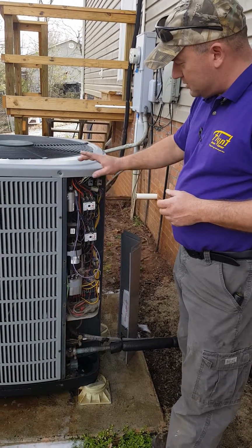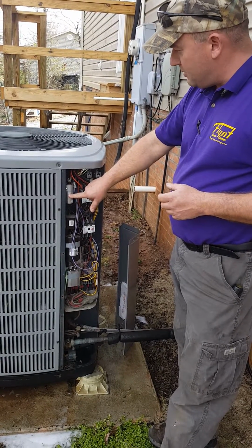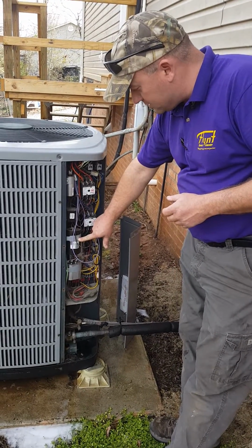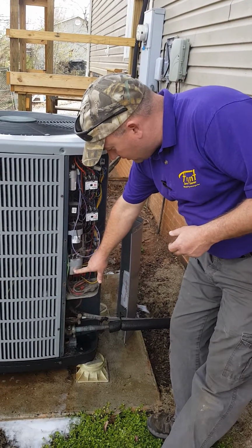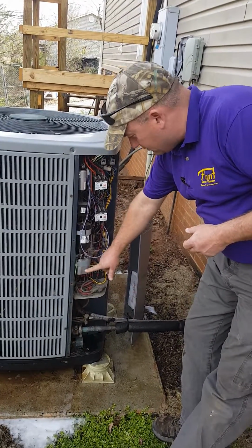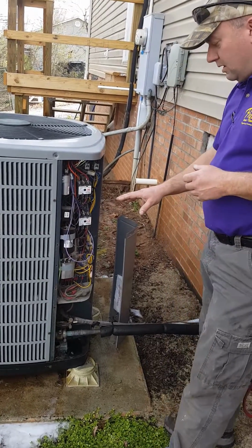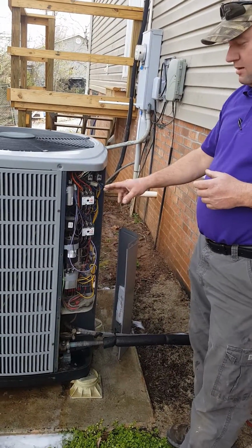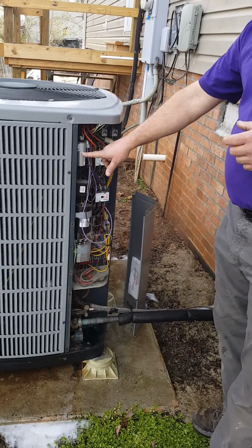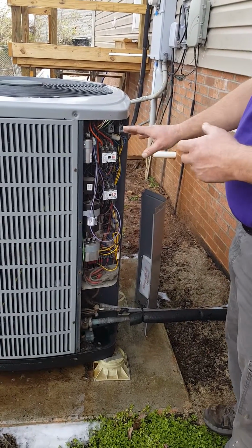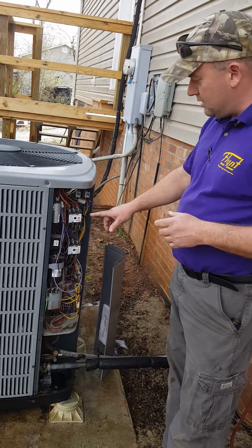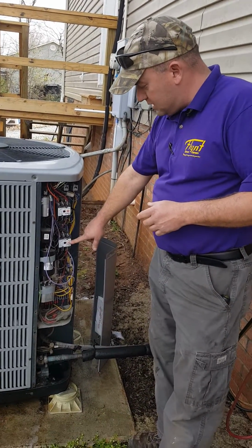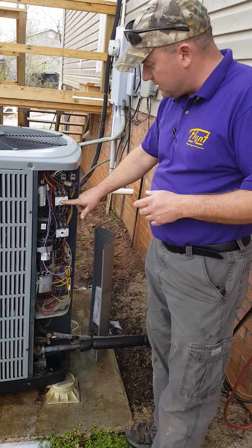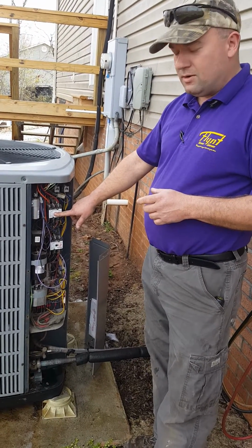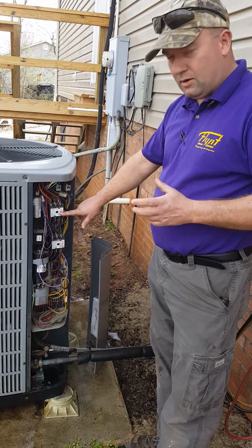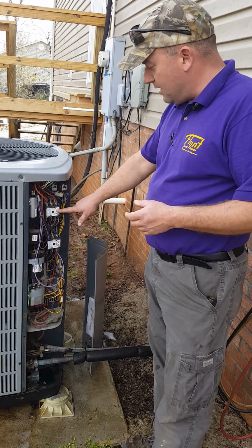This particular unit has a run capacitor for the fan motor, a start capacitor for the compressor, and another run capacitor for the compressor. We're going to check the microfarad reading on each one of those and compare it to the factory ratings, plus or minus 10%. Anything different, that capacitor would need to be replaced. This unit has two sets of contactors on it. We're also going to check the contacts on each one, making sure they're not burnt or pitted, and then recommend replacing if needed.